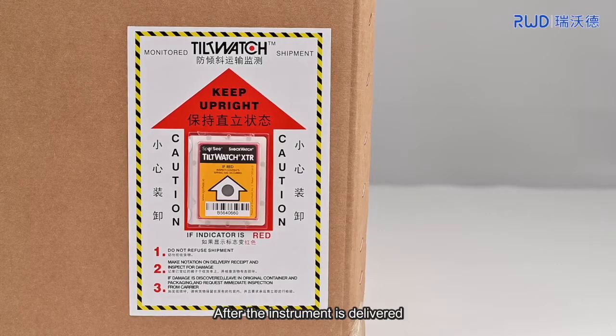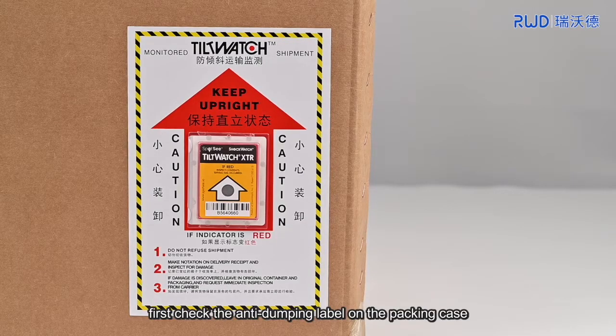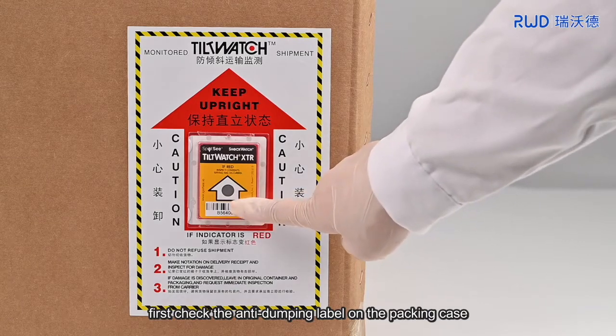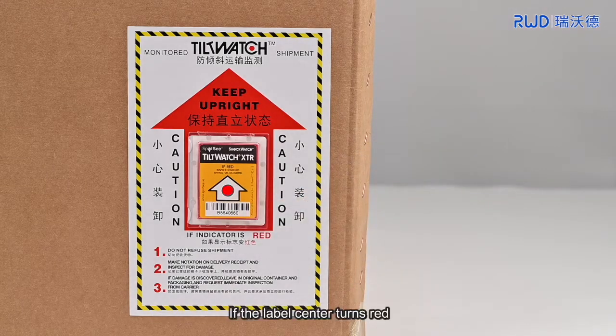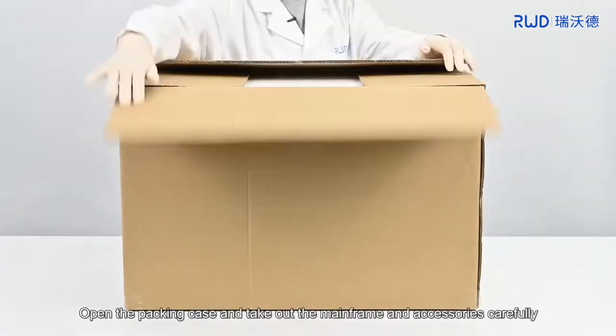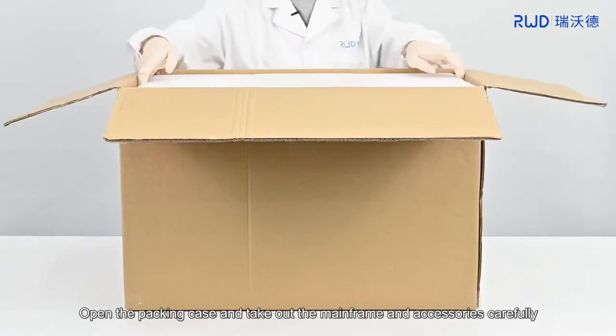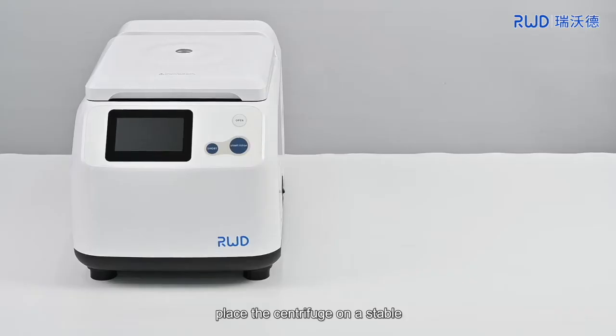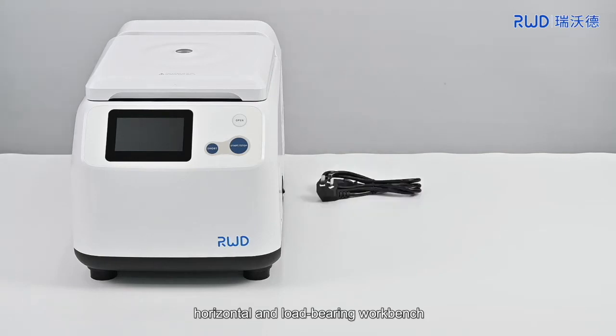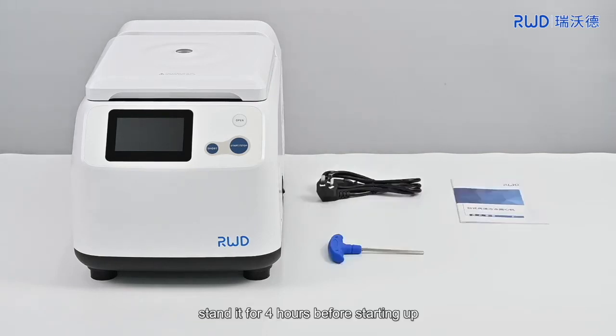After the instrument is delivered, first check the anti-dumping label on the packing case. If the label center turns red, please contact RWD staff in time. Open the packing case and take out the mainframe and accessories carefully. Place the centrifuge on a stable, horizontal, and load-bearing workbench. Stand it for 4 hours before starting up.